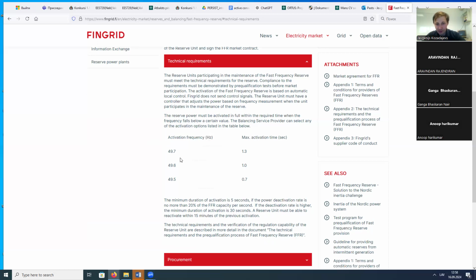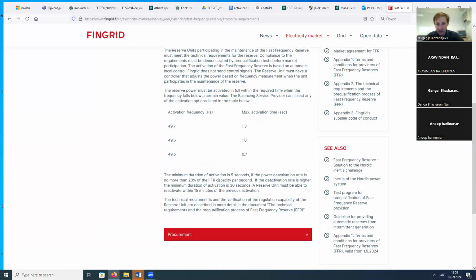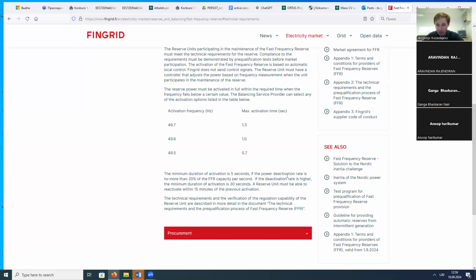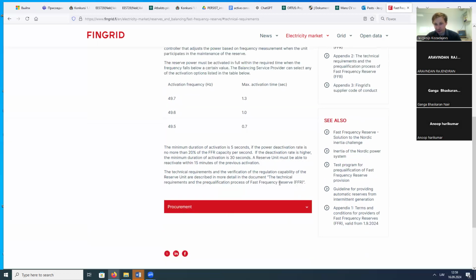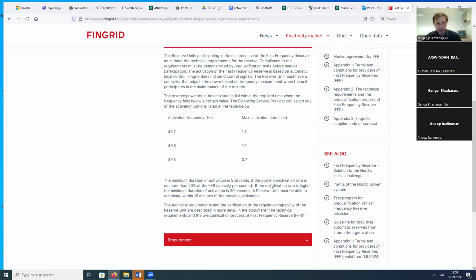Okay, so this is activation, max activation time, you see the criteria. You need to follow the frequency and you have a time limit for how fast you should react. The minimum duration of activation is 5 seconds. The power deactivation rate is no more than 20% of the FFR capacity per second. If the deactivation rate is higher, the minimum duration of activation is 30 seconds. The reserve unit must be able to reactivate within 15 minutes of the previous action. The technical requirements and the verification of the regulation capability of the reserve unit are described in more detail in the document. If you're interested, you can look at the documentation about these procurements in detail.